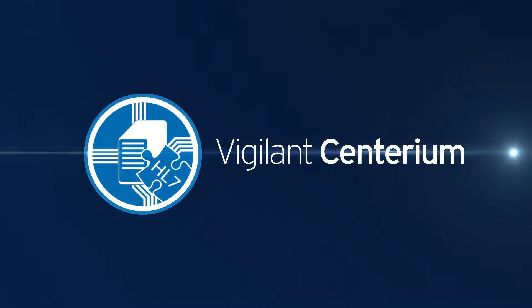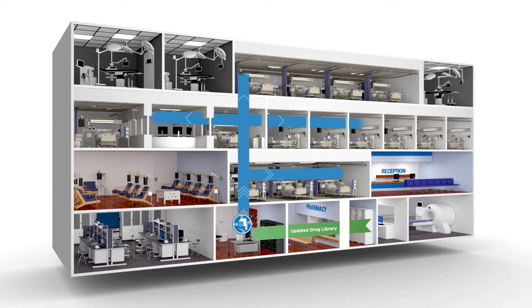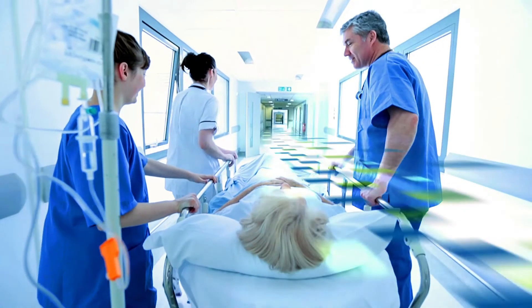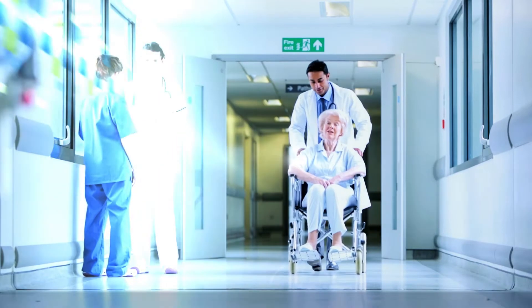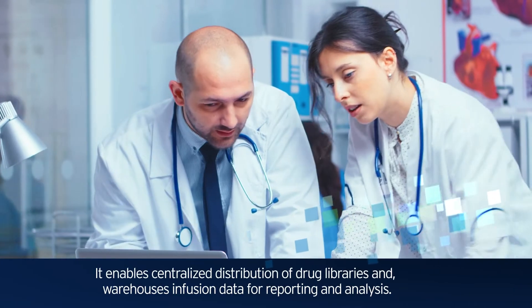Vigilant Centerium is the data management platform that provides wireless connectivity between up to 4,500 Agilia Connect pumps and Vigilant MasterMed and Vigilant Insight software. It enables centralized distribution of drug libraries and warehouses infusion data for reporting and analysis.